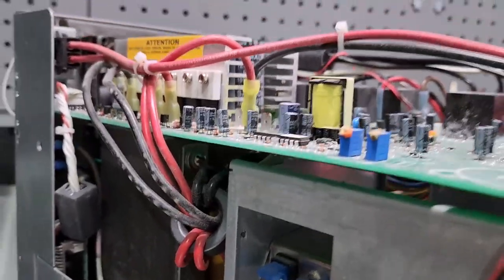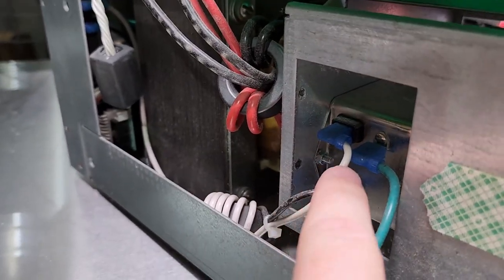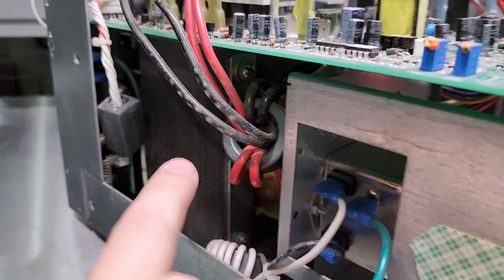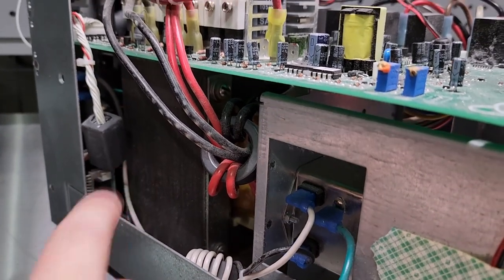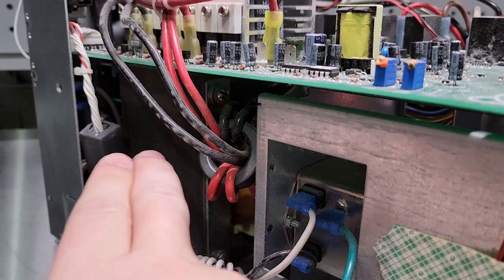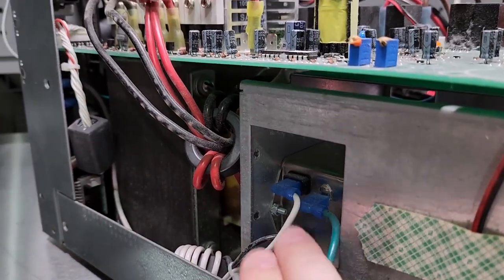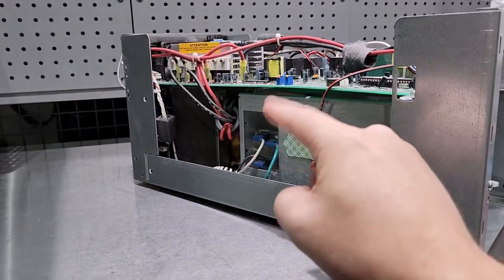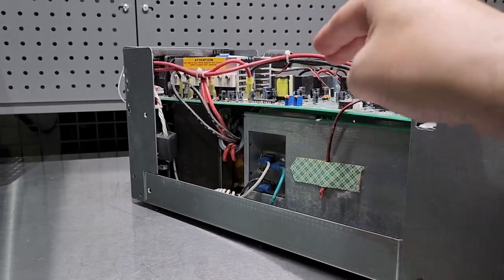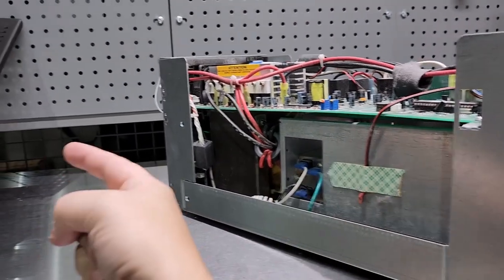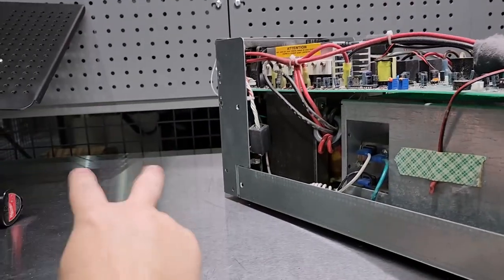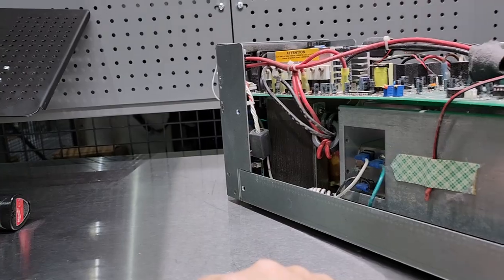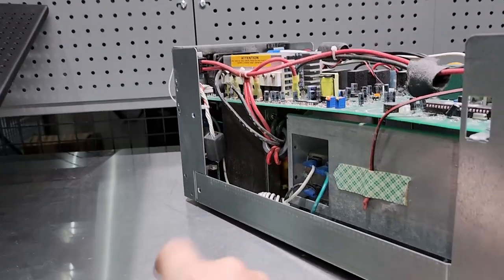The EMI filter is there to mainly make sure that a lot of the noise that's generated here does not go back out to mains. Mains comes into the EMI filter, and then from here it goes to the transformer. If you have really garbage waveforms coming into a transformer or going out of the transformer, the last thing you want is for that interference or the noise from the choppers to go back out on your AC mains. Any device that's plugged into that circuit would also pick up that noise, which could create problems.